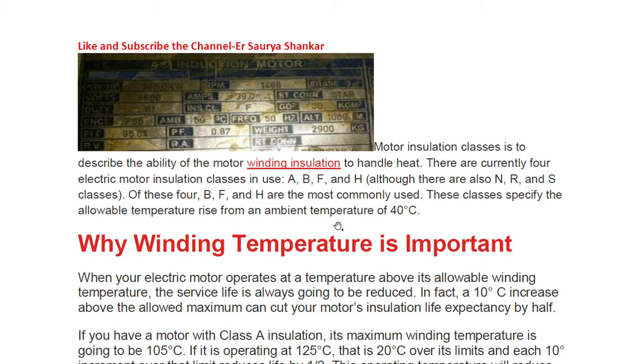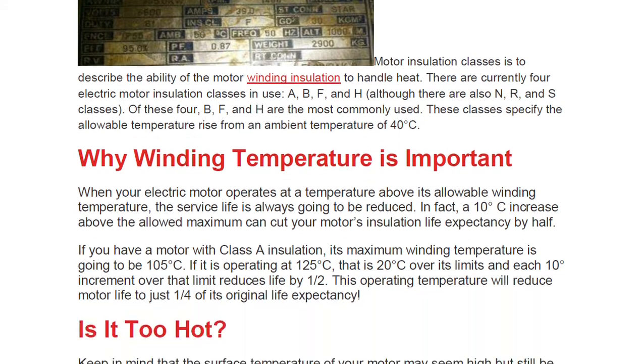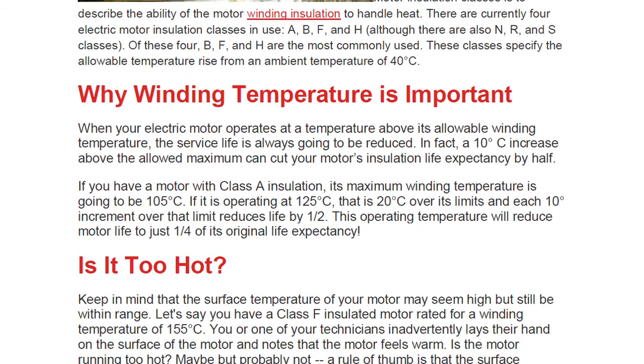These classes specify the allowable temperature rise from an ambient temperature of 40°C. So from a base ambient of 40°C, they describe what the permissible rise above that is. This is why understanding insulation class is important.